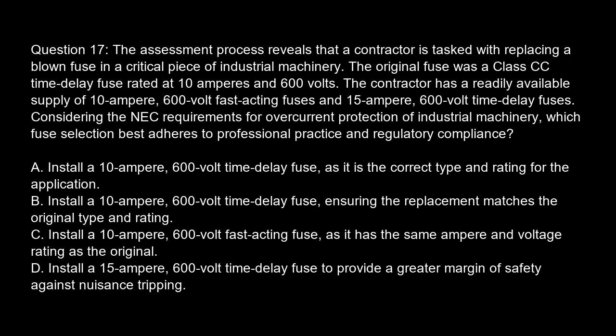Question 17. The assessment process reveals that a contractor is tasked with replacing a blown fuse in a critical piece of industrial machinery. The original fuse was a Class CC time-delay fuse rated at 10 amperes and 600 volts. The contractor has a readily available supply of 10 ampere, 600 volt fast-acting fuses and 15 ampere, 600 volt time delay fuses. Considering the NEC requirements for overcurrent protection of industrial machinery, which fuse selection best adheres to professional practice and regulatory compliance?